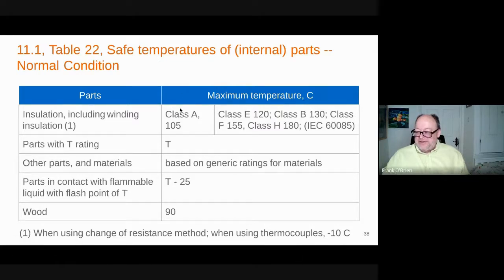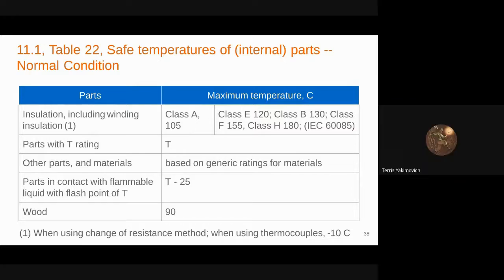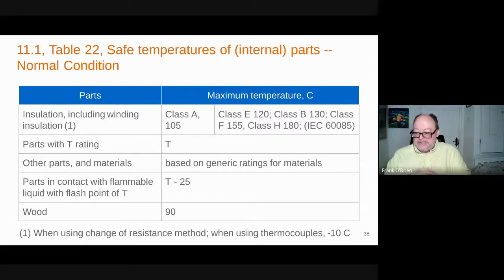So when we check temperatures on magnetics, motors and transformers, we check it with a thermocouple, which is how we normally check temperatures. We have to be actually 10 degrees C less than the limit, because thermocouples are checking the outside surface temperature of the transformer inside the enclosure, but on the outside of the transformer, and inside could be hotter. And so with resistance methods, we get an average, and the limit applies for change in resistance. So if you're copper or aluminum, say copper, we know its conductivity, and if we knew the resistance cold and hot, we actually know that temperature rise. And so there's a formula. But we generally just use thermocouples, and so we have to be 10 under the limit because we're lazy.